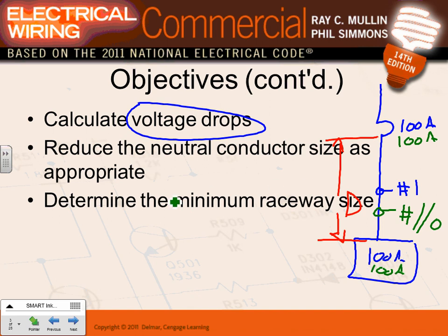Determine the raceway size, the conductor, and then the neutral size. We'll talk about the neutral. We size our neutral based on the unbalanced load. And I told you guys the rules for the neutral. Up to 200 amp, 225 amp panel, for the neutral, don't even mess with it. Higher than 200, 225 amp panel, maybe 250, 300, you start derating. If you don't know the load, you start derating based on, remember, 70% of the 200. If you have the actual load, then you just use the load. Cool? So that's what we're going to be doing, and then sizing the raceways to fit that.